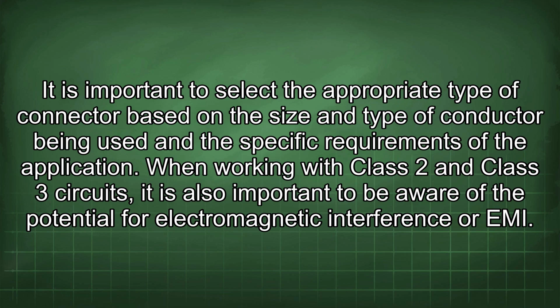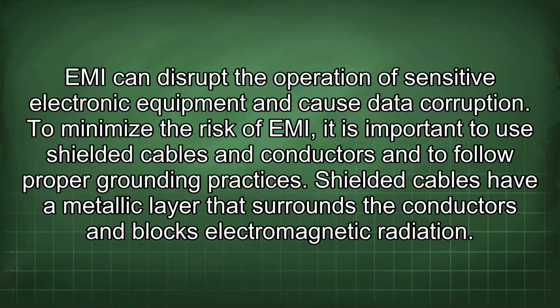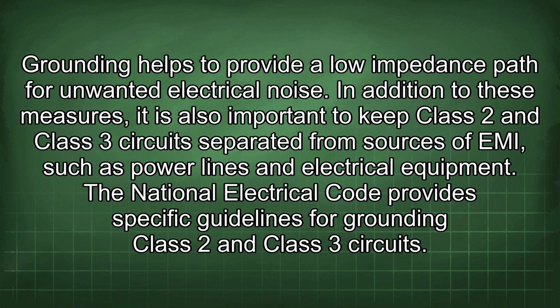When working with Class 2 and Class 3 circuits, it is also important to be aware of the potential for electromagnetic interference, or EMI. EMI can disrupt the operation of sensitive electronic equipment and cause data corruption. To minimize the risk of EMI, it is important to use shielded cables and conductors and to follow proper grounding practices. Shielded cables have a metallic layer that surrounds the conductors and blocks electromagnetic radiation. Grounding helps to provide a low impedance path for unwanted electrical noise. In addition to these measures, it is also important to keep Class 2 and Class 3 circuits separated from sources of EMI, such as power lines and electrical equipment.